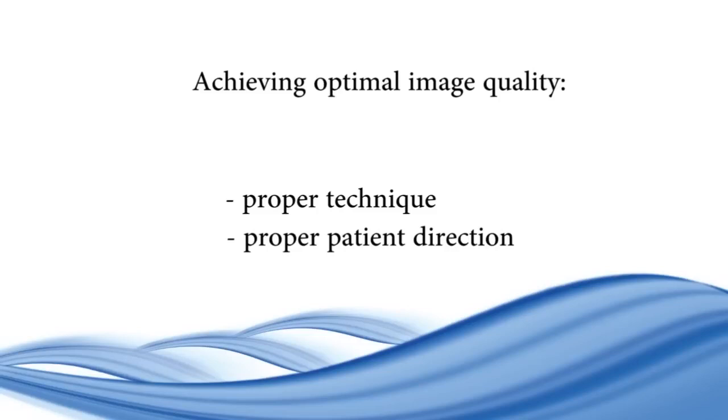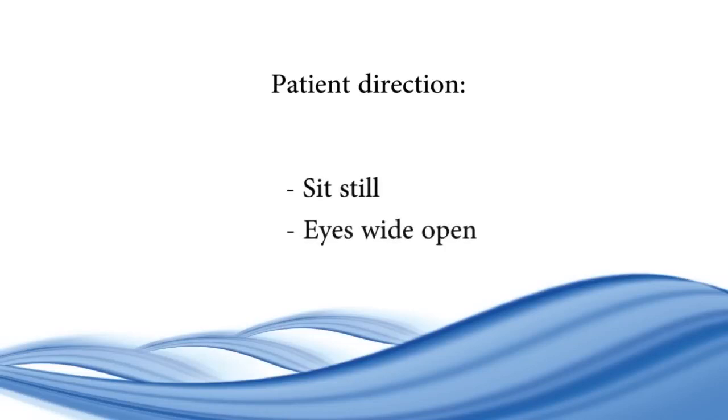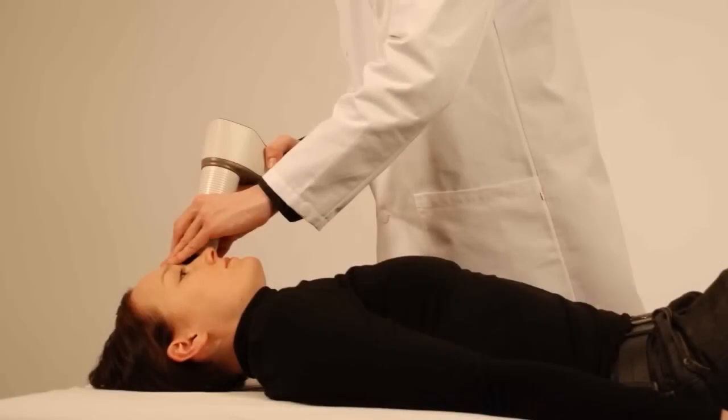To ensure the camera is stable for the image, it is recommended that both the patient and examiner are seated during the exam. The patient should be asked to sit still with their eyes as wide open as possible and focus on a target on the wall two to three meters behind the examiner so that the patient's eyes will target to infinity. It is also possible to use the camera for patients lying down.